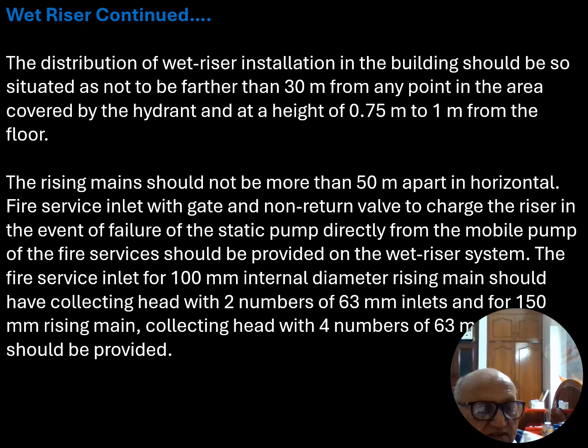The rising mains should not be more than 50 meter apart in horizontal distance. A fire service inlet with gate and non-return valve to charge the riser directly from the mobile pump of the fire service, in the event of failure of a static pump, should be provided on the wet riser system. The fire service inlet for a 100 mm internal diameter riser main should have a collecting head with two numbers of 63 mm inlets, and for a 150 mm riser main, a collecting head with four numbers of 63 mm inlets should be provided.